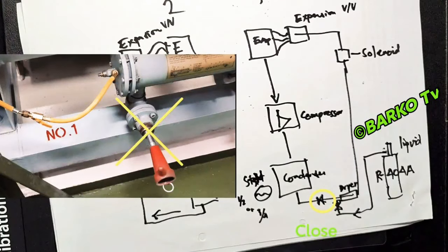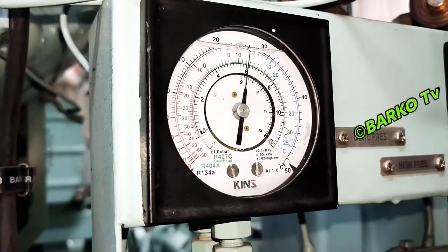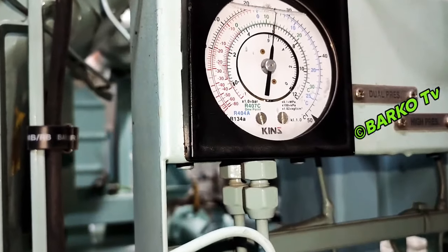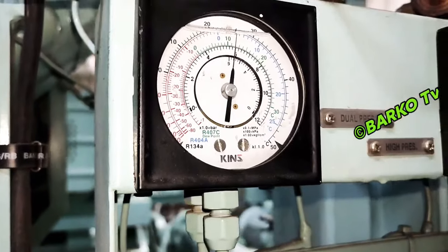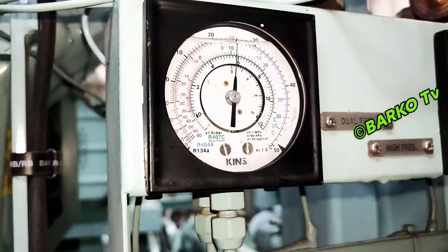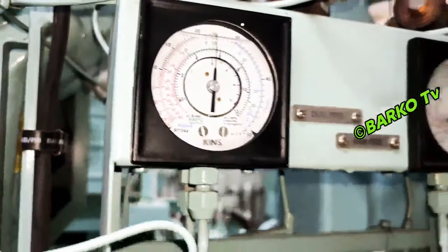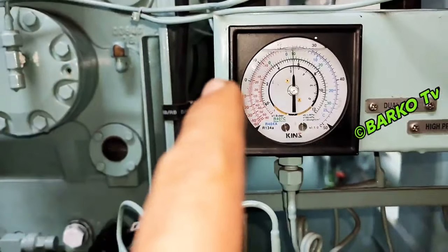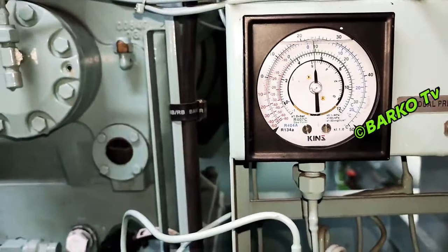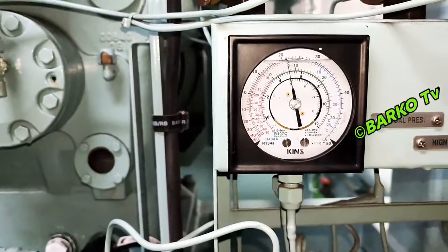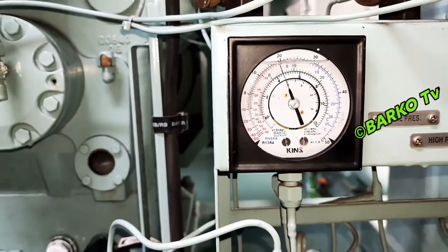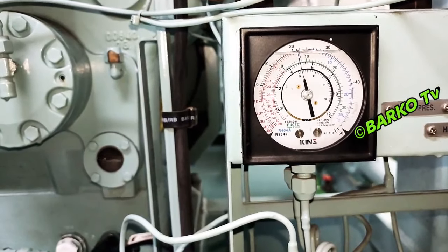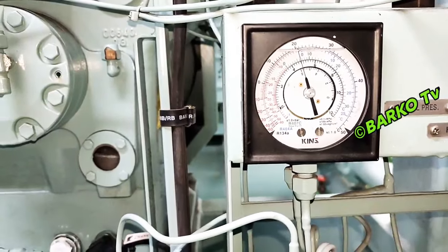And then the compressor is running. It will accumulate all refrigerant at the condenser/receiver. After you close the isolation valve, our compressor starts sucking all refrigerant and puts it into the receiver. Right now the pressure gauge at the low side is getting lower, and you wait for the low suction pressure switch to trigger shutdown, and then start by opening the liquid valve at the bottle. Okay, we will wait for the low suction to trigger.